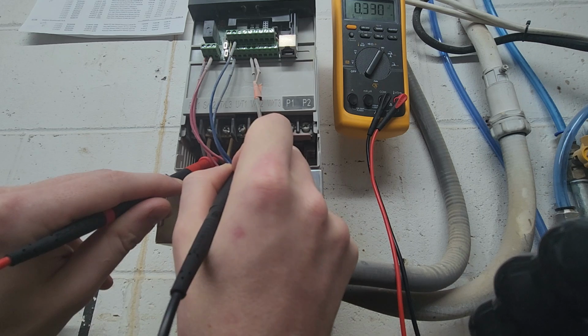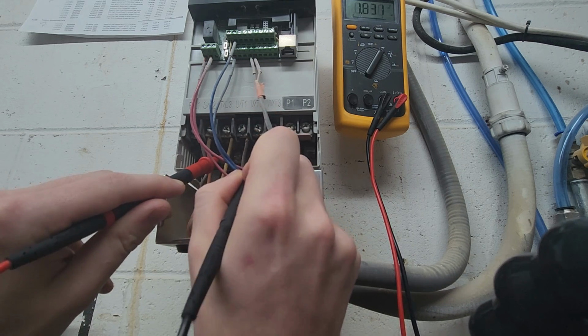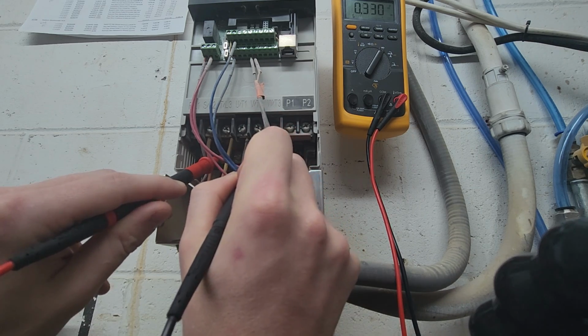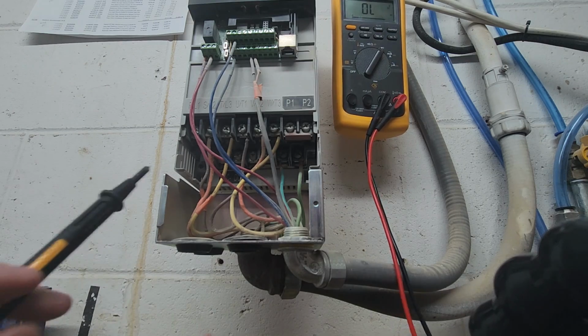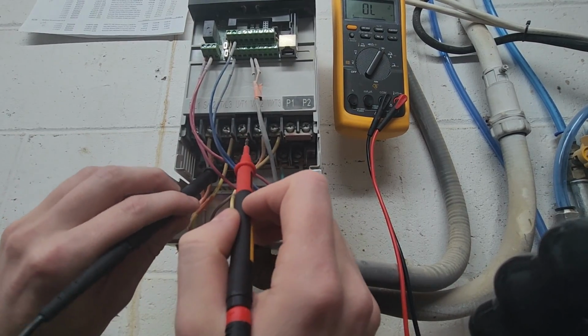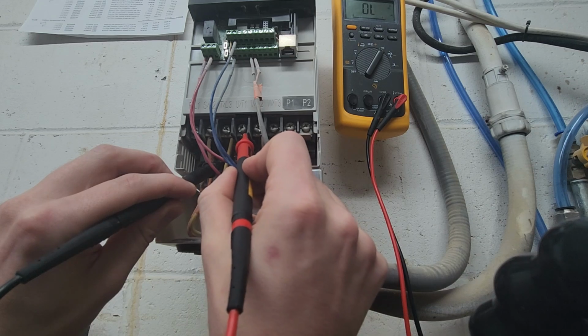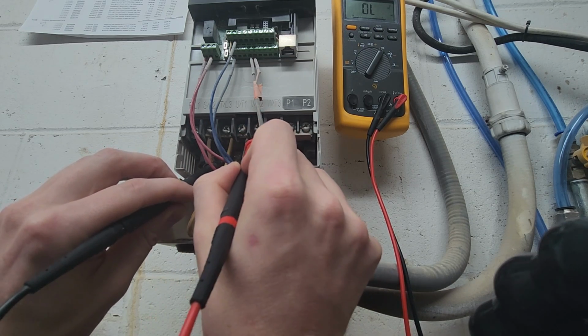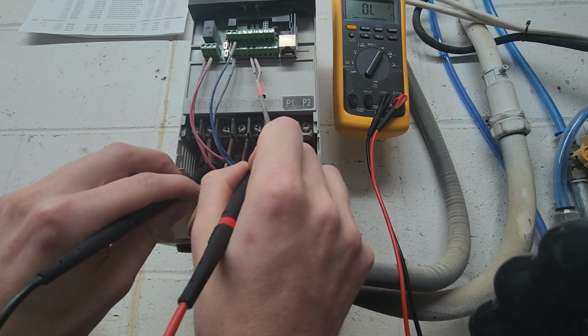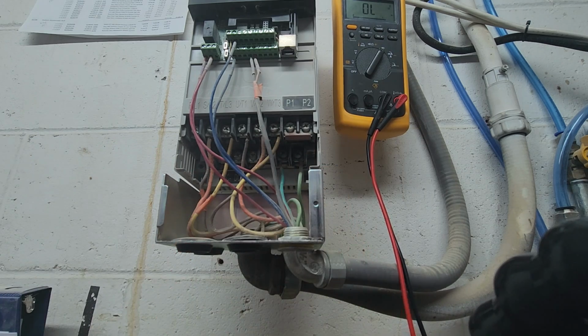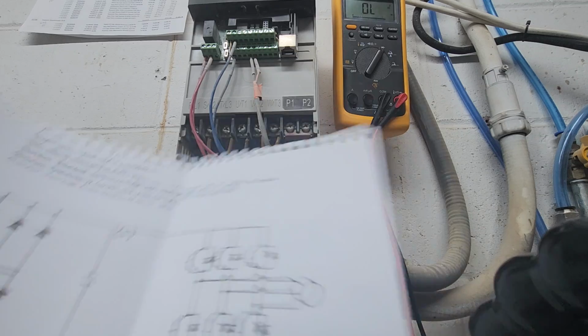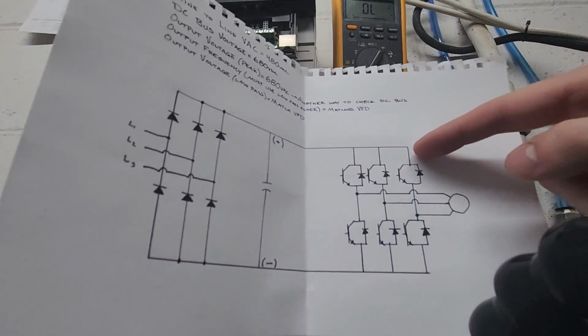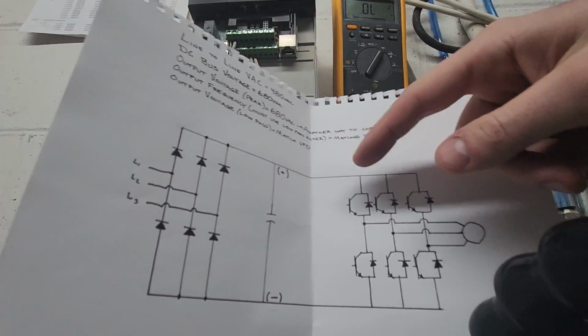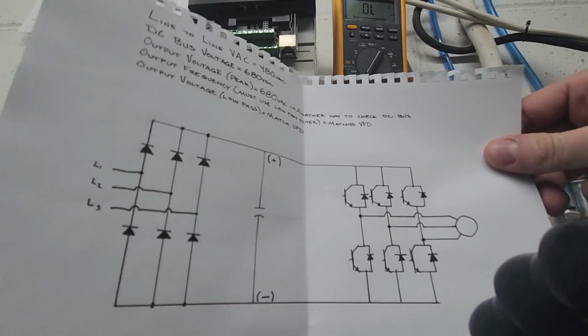So positive probe on DC bus negative, and negative probe on our outputs, 0.32, 0.33, 0.33. That's perfect. Let's check them going the other way. We shouldn't see anything here. So negative on DC bus negative and positive on your 3 outputs. And we're over limit on all 3. And that's perfect. That means that all of our diodes, we've just gone through every single diode on this VFD, at least the main ones, and they've all checked out properly.